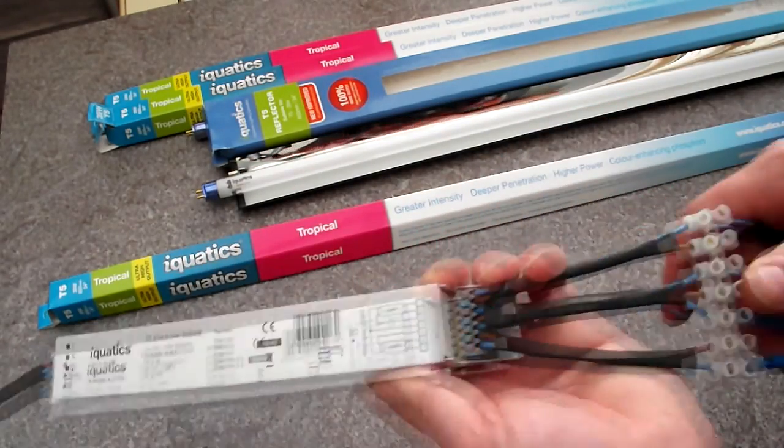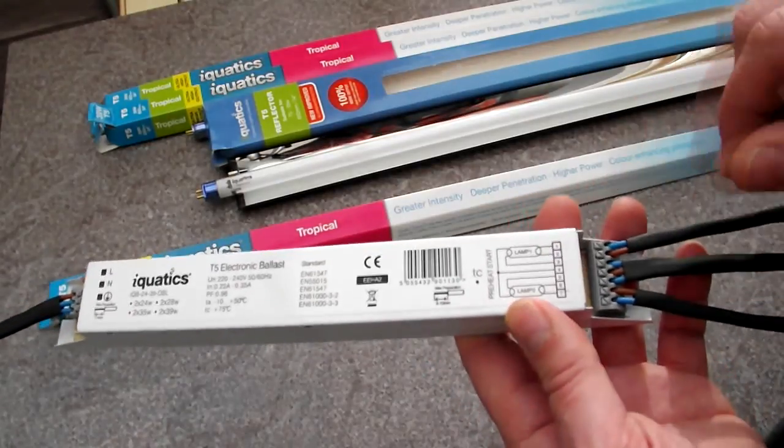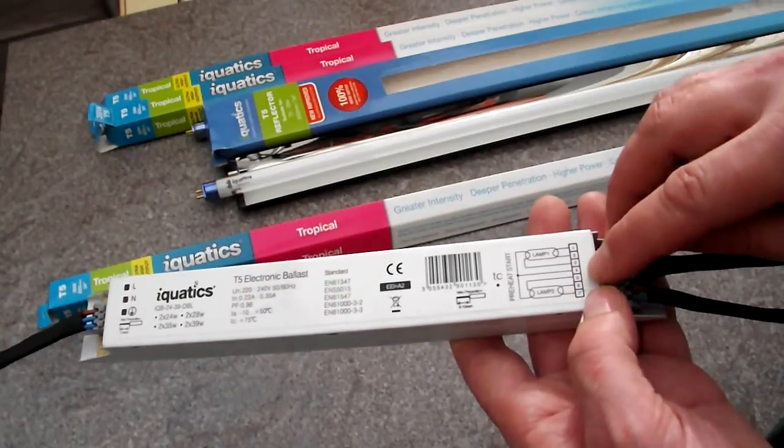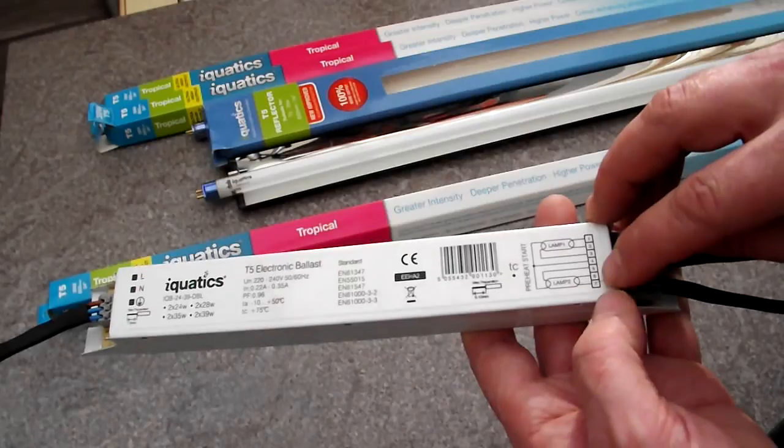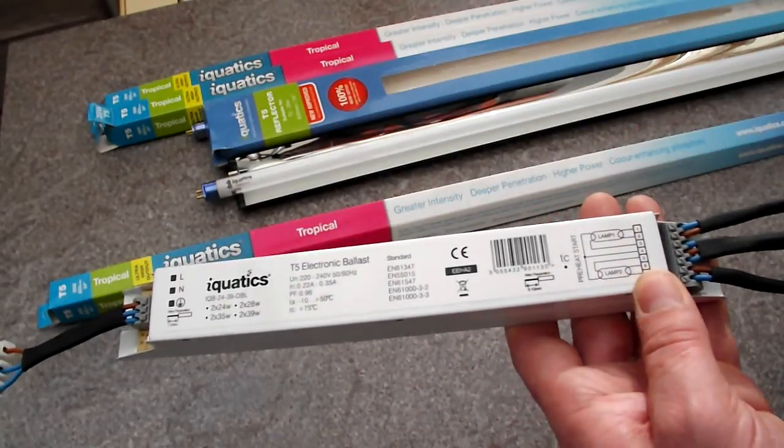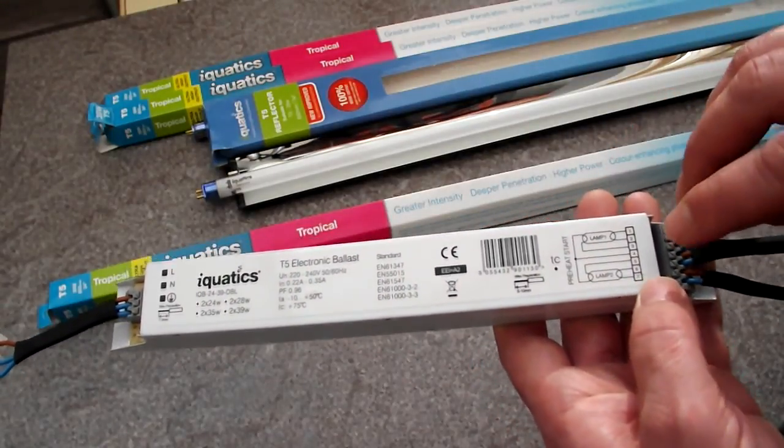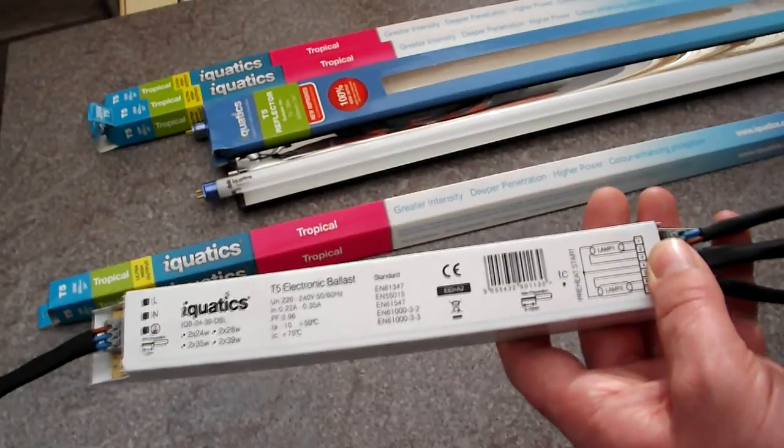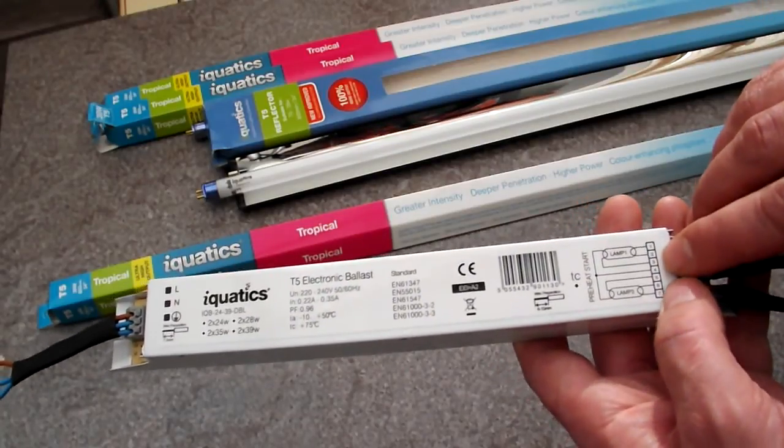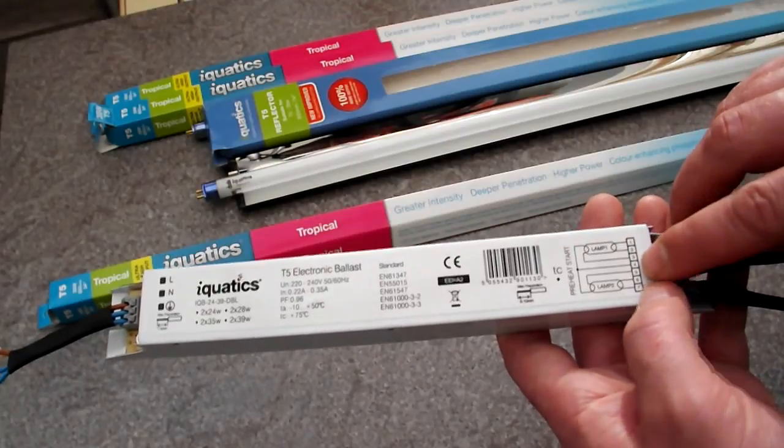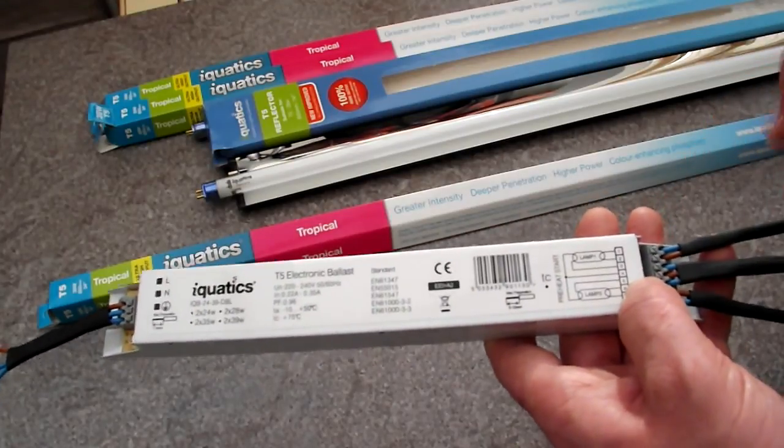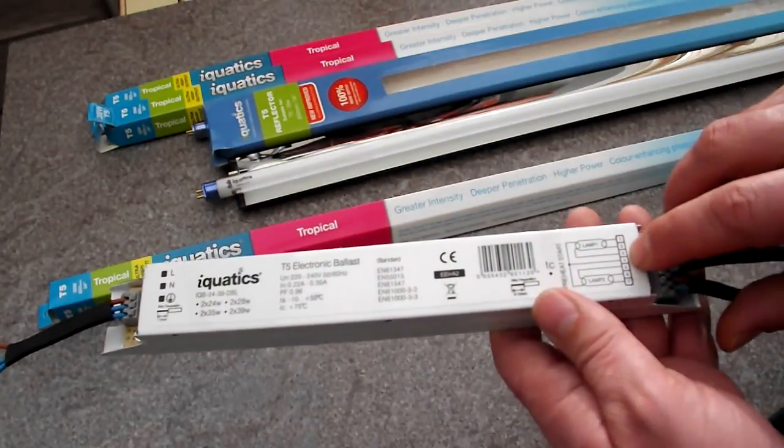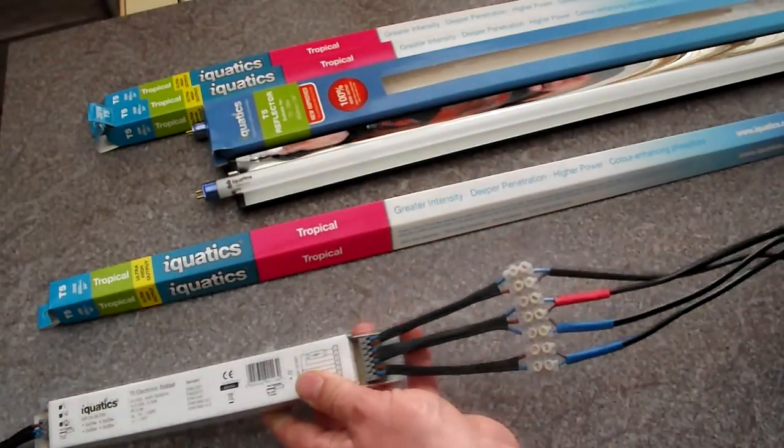On the other end, you've got the seven ports for the lamps. Now, slots one and two go to one side of the lamp on lamp one. Slots six and seven go to the same side of the lamp on lamp two. And then you've got three, four and five in the middle. Now these go to the opposite side on both lamps. You've got three and five, which one cable from each of the lamps go into. And then you've got number four, which they share.